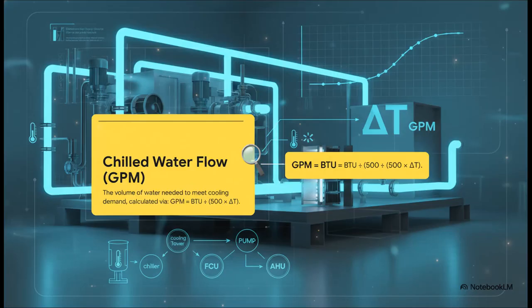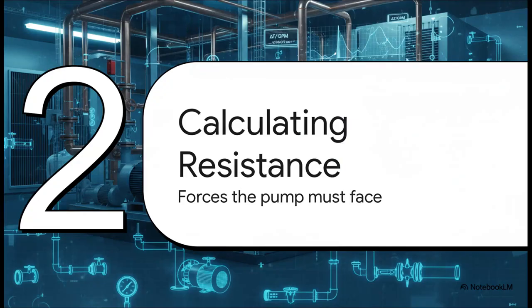Okay, so the very first question an engineer has to tackle is, how much water do we actually need to move? This is our flow rate, and we measure it in gallons per minute, or GPM. To figure it out, we use this absolutely fundamental formula. It connects the building's total cooling needs, that's the BTUs, with the temperature difference between the supply and return water, which is what we call the ΔT. If you know those two things, this formula tells you exactly how many gallons per minute you need to be pumping.